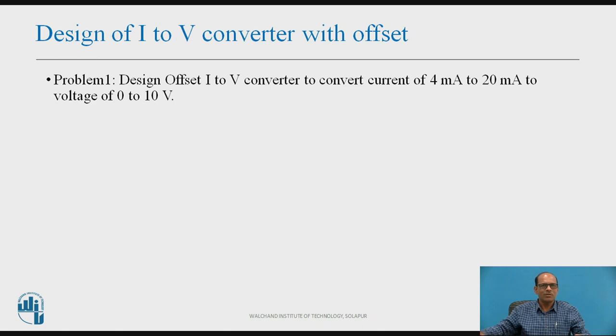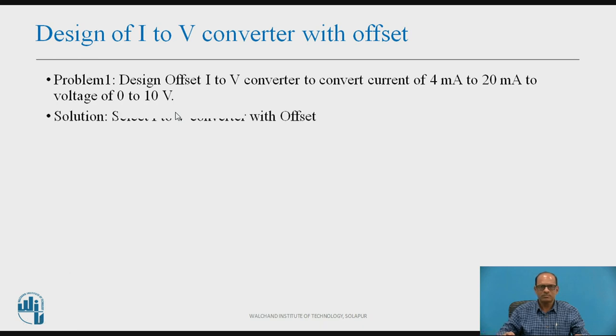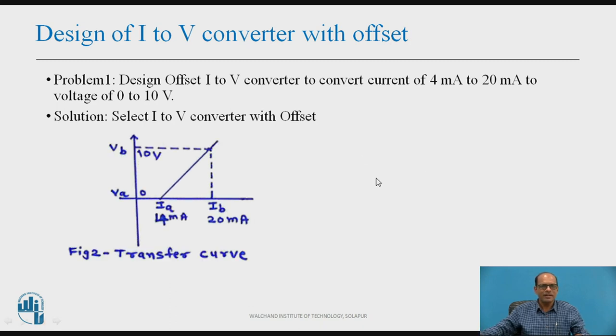Now let us proceed further for the design of I-to-V converter with offset problems. Problem 1: design an offset I-to-V converter to convert a current of 4 mA to 20 mA into a voltage of 0 to 10 V. Solution: select I-to-V converter with offset as the basic circuit. From the given data, the transfer curve can be plotted as shown in figure — input is 4 mA to 20 mA and the output is 0 to 10 V.